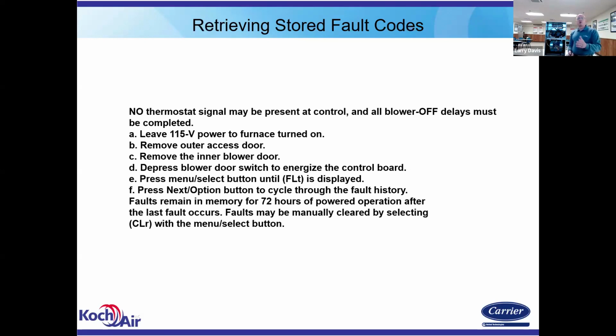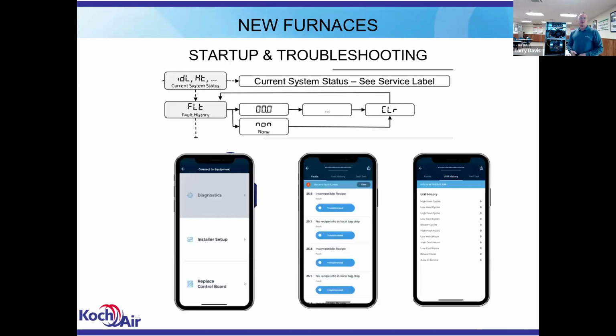It won't clear out the counts of faults. That'll stay in there. So here again, diagnostics, you connect to it, diagnostics, it pulls up a list of fault codes. Reset, you see at the top of that center screenshot where it says clear, you can clear those out. And then there's your unit history, your cycles, fault codes. And again, you can generate that report and send it back to the office. Okay.